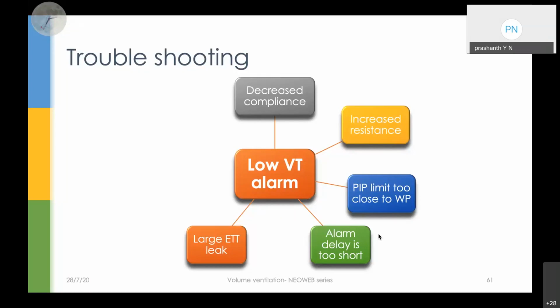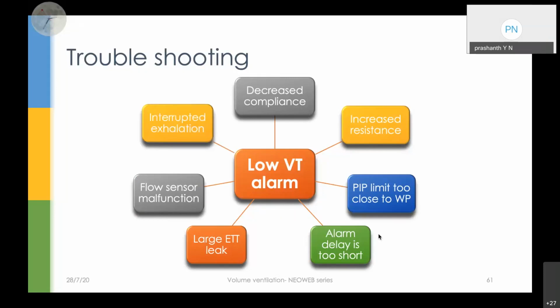So you need to see if you have used the appropriate ET tube, or if the tube has come out, or if there is any problem in the circuit. And the other thing is, if the flow sensor is not functioning well, obviously you will have false low VT alarms. And this is what we see in babies: probably the baby has seizures, or the baby is crying so vigorously that the ventilator is not able to push the volume into the lungs, because the baby is actively expiring all the time. So the ventilator probably will give VT alarms. So we need to see what is happening to the baby, whether the baby is having seizures or breath holding, or is actively crying. We need to tackle the cause rather than just looking at the alarms.